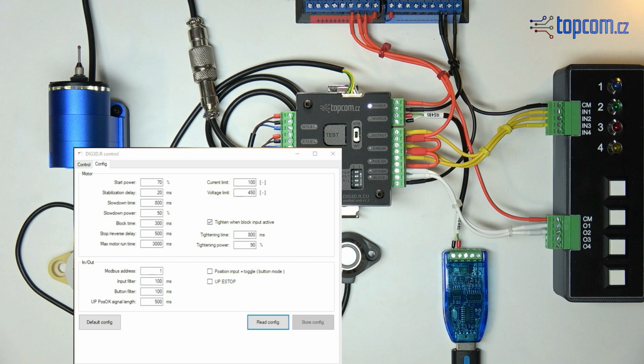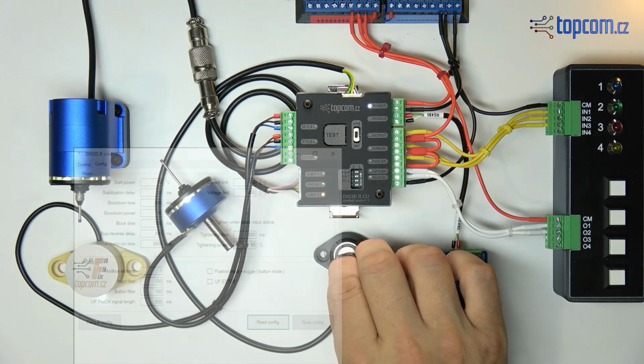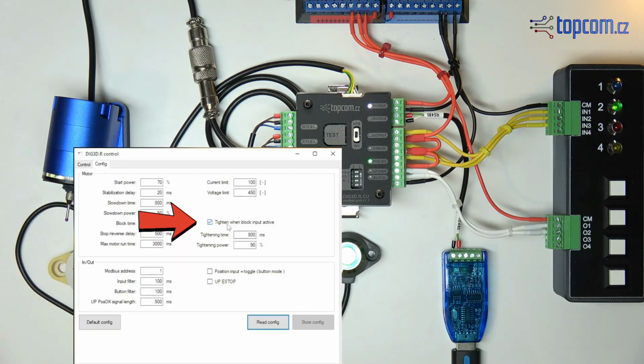The first is the option to retighten the probe position every time the block signal is activated. This signal always logically precedes any measurement with the probe, as it disables the probe guard function. If for any reason the rotated probe becomes slightly loose or misaligned, this feature ensures it is always firmly repositioned into the correct working position. If the function is disabled, no retightening will occur.